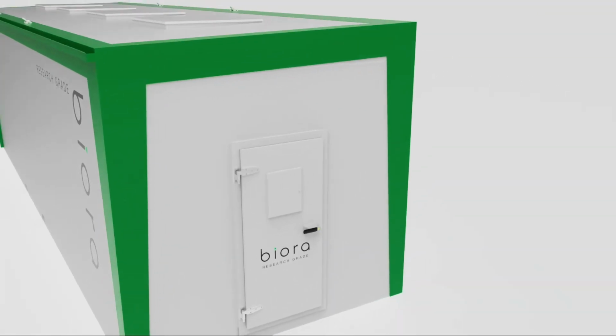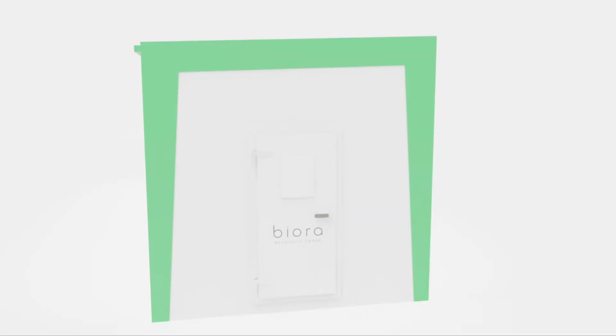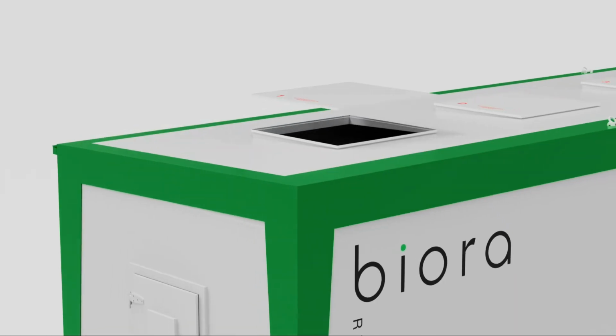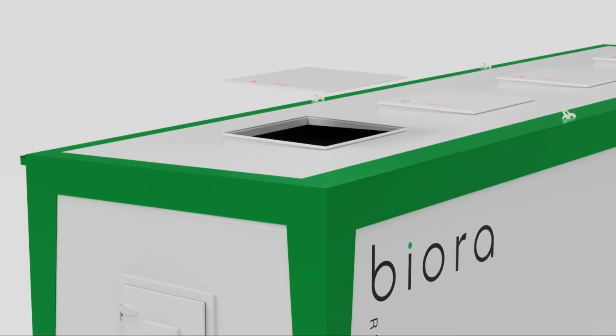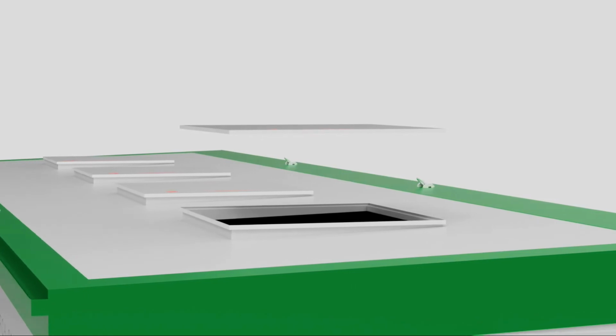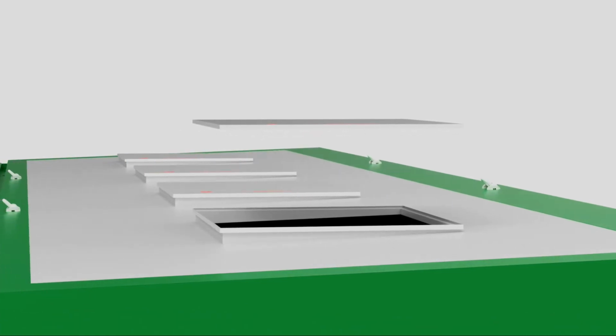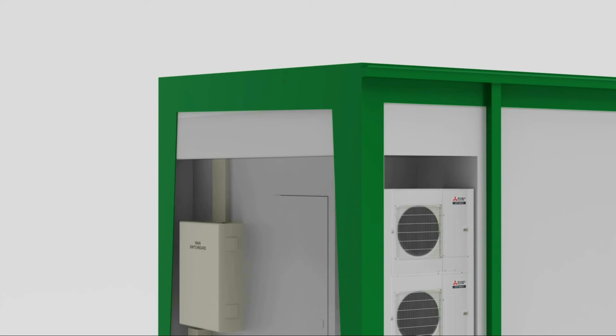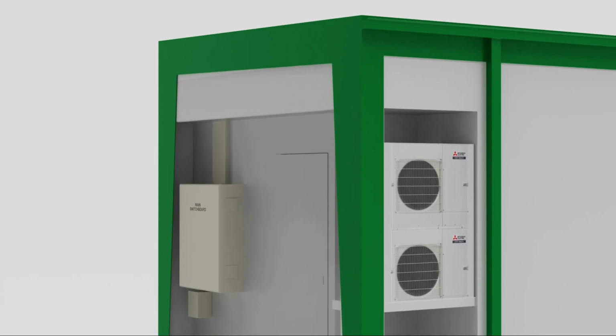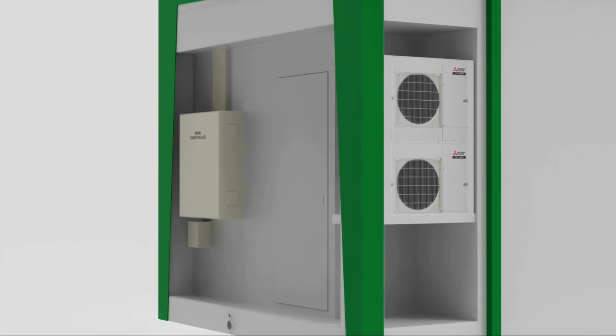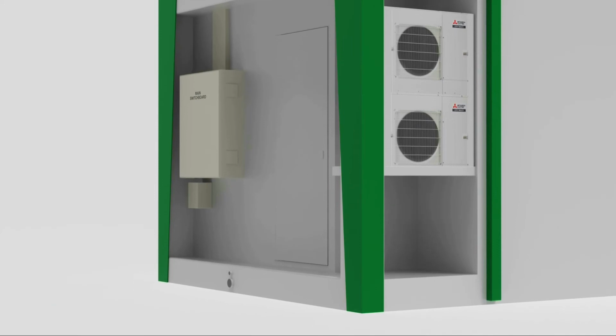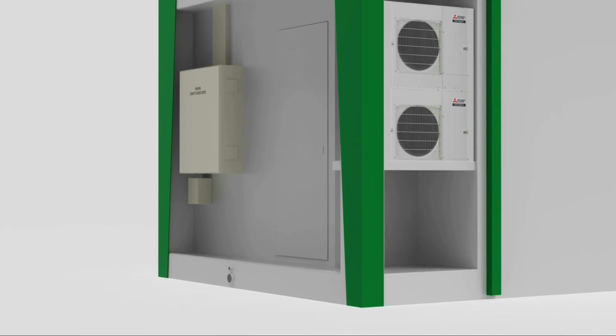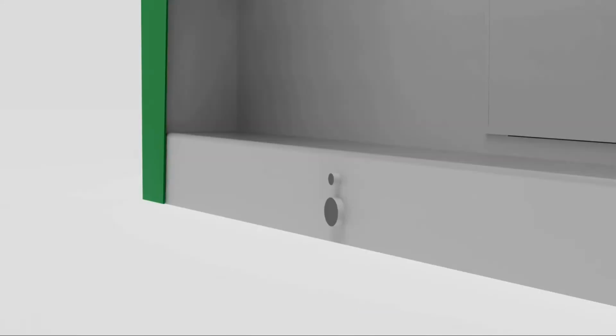As we move around the exterior of the Biora chamber, there are four external hatches built into the chamber roof. This means that apart from lighting, all chamber maintenance can be done outside of the chamber's containment boundary. Here we have the outdoor air conditioning unit, switchboard and main isolator. This allows for an easy connection to an external power source and Ethernet for remote connectivity. Here are the connections for mains water supply and drainage.